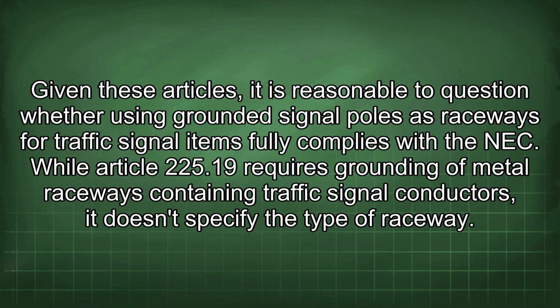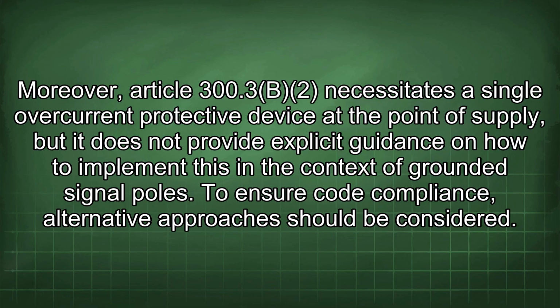225.19 requires grounding of metal raceways containing traffic signal conductors, it doesn't specify the type of raceway. Moreover, Article 300.3b2 necessitates a single overcurrent protective device at the point of supply, but it does not provide explicit guidance on how to implement this in the context of grounded signal poles. To ensure code compliance, alternative approaches should be considered.